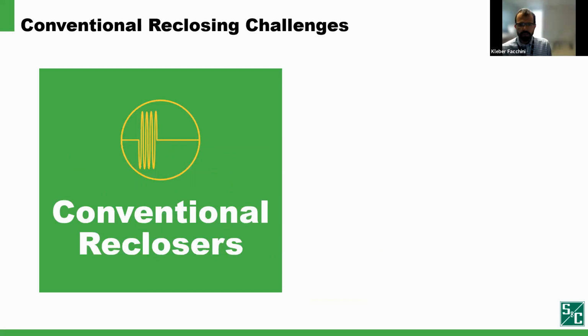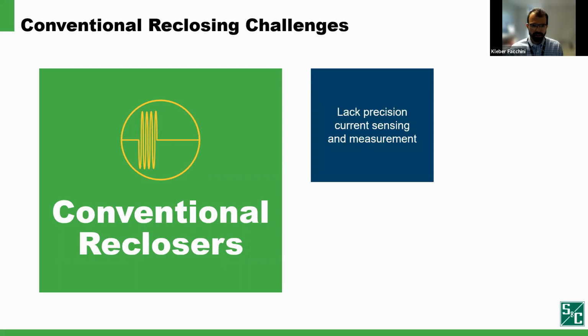When fault interrupters are used to accomplish segmentation, there is a desire to achieve coordination among them. Therefore, an effort to coordinate multiple time current characteristic curves, also known as TCC, is required. However, when using reclosers for segmentation, often users are faced with a few challenges. As these devices lack high end-to-end current sensing accuracy, only 2 or 3 conventional series reclosers can be properly time current coordinated with the substation circuit breaker, and if more are used, miscoordination over tripping typically occurs, and that's what we saw in pole 1.